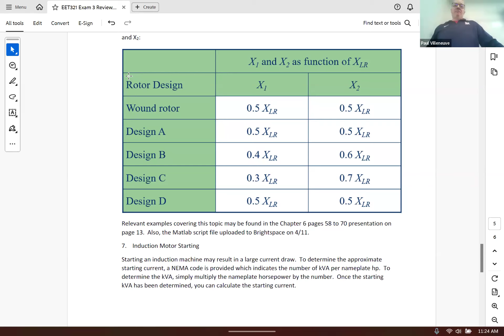And then if you start a motor, you've got to look at the KVA code. The KVA code, which tells you the number of KVA per nameplate horsepower, tells you how many KVA you need to start, so you can calculate the current. So if your system can handle a large inrush, start it across the line. That's the cheapest, best way to do it.